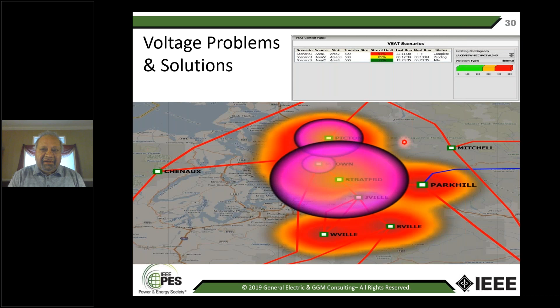Here's an example of providing information to fix problems on the grid. Say you have a low voltage situation over here—now we have a tool where you use your cursor to freehand lasso an area and say, show me all my reactive resources in that area that will let me fix the problem. It shows the units, capacitors, reactors, SVS in the area, and now the operator can either call up a substation operator or switch in a capacitor to fix the problem.